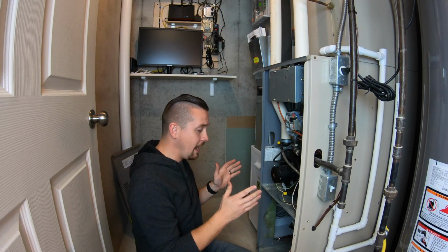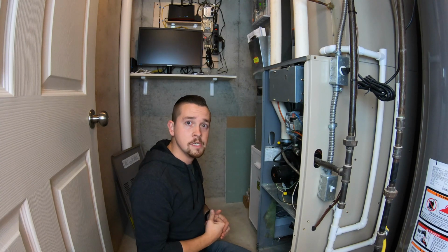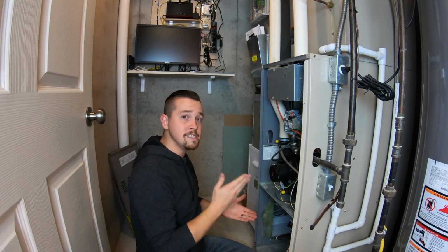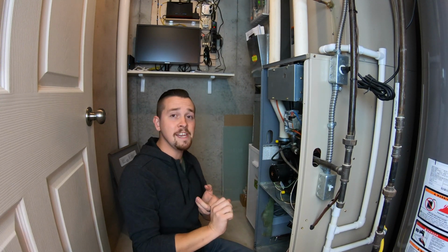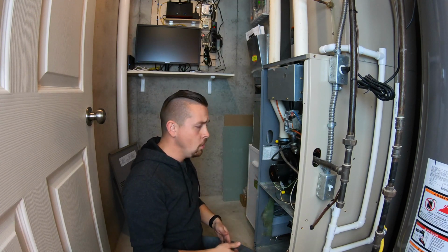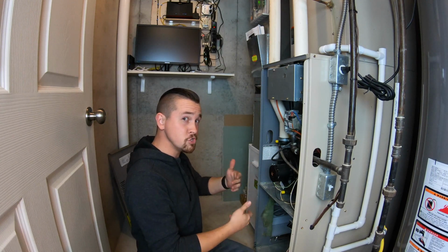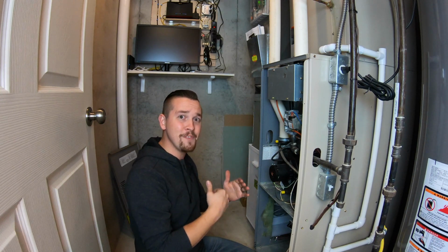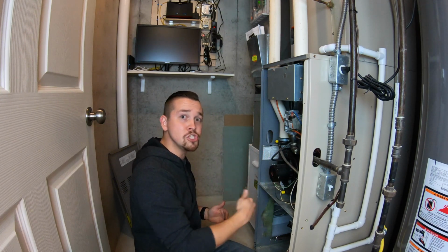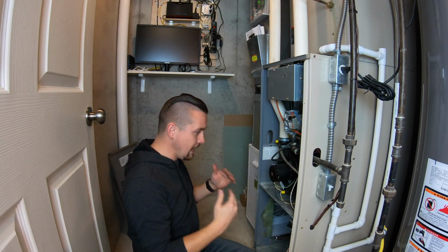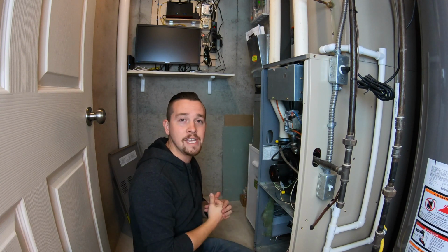Additionally, you might not have a working blower motor. If for some reason your circuit board isn't sending power to the motor, or the motor is getting power but it's still not coming on, or the capacitor's failed, so maybe the motor's trying to start but it doesn't have the oomph that it needs for the capacitor to push it to go, then that can cause your furnace to get too hot and overheat as well.